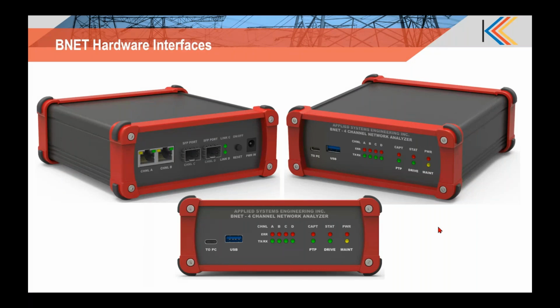For the full simulation, we'll have to depend on the IED Smart tool. ASE61850 IED Smart comes as a simulation tool for the entire substation, and there you will be able to simulate a larger number of IEDs. But we don't have sample value functionality there. Only GOOSE and MMS capabilities can be simulated. So sample value can only be done through BNET.